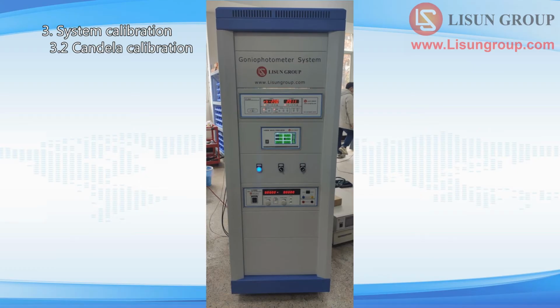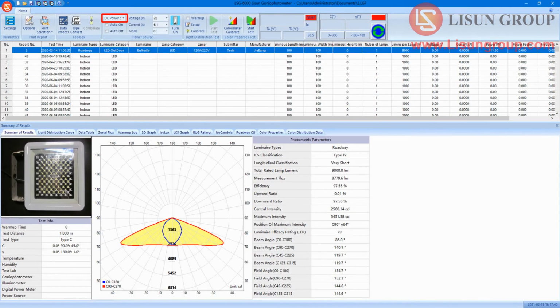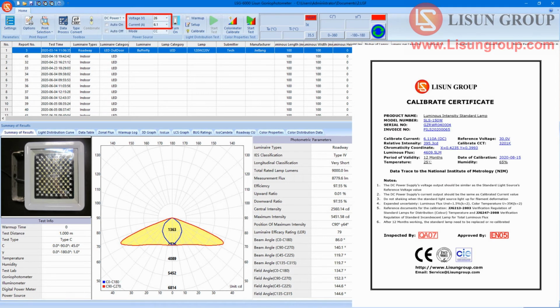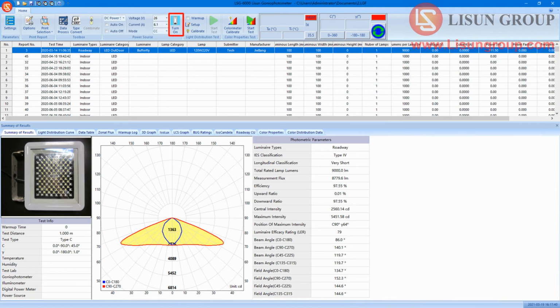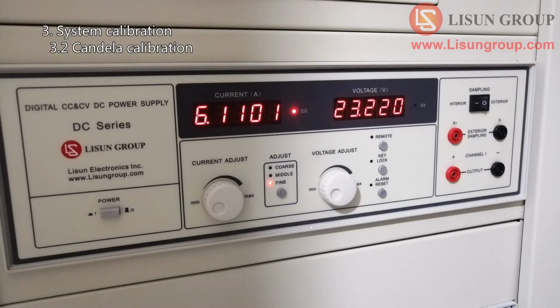Our standard lamps are constant current DC lamps. Turn the AC-DC switch on the cabinet to DC. Choose the DC model on the navigation of the software. Input the current and voltage according to the certification. Please note that you need to use CC, constant current, mode. Click to turn on the standard lamp. You can also confirm the DC source whether output the same constant current as the one you input.